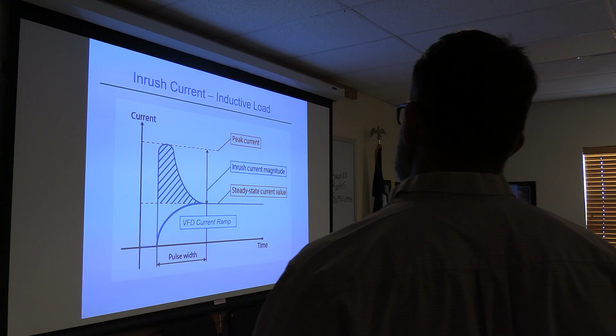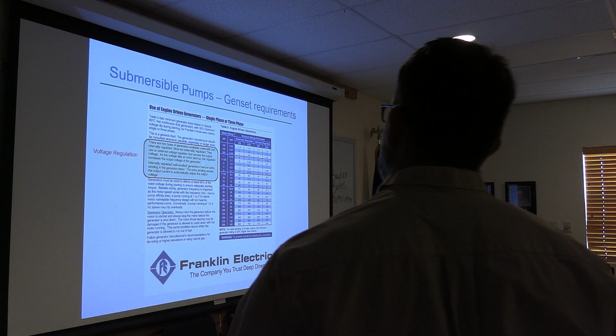And so we need to take advantage of that by using a variable frequency drive or a soft start. And I would say that with the genset in every application. I don't think there's an application where it would be beneficial to have an across-the-line starter there at all. It does come with some caution though. Since you're probably looking at submersibles, we'll go a little farther forward.